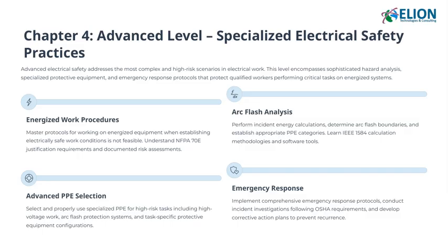Next, we move to arc flash analysis. Performing incident energy calculations helps us determine arc flash boundaries and select appropriate PPE categories. Learning how to apply IEEE 1584 calculation methodologies and utilizing software tools can significantly improve our accuracy and safety in these assessments. Then, there's advanced PPE selection. For high-risk tasks like high-voltage work or arc flash protection, choosing the right specialized PPE is critical. Proper use and correct configurations of protective equipment can make a big difference in safety outcomes during dangerous situations.